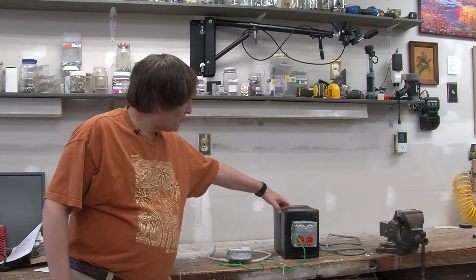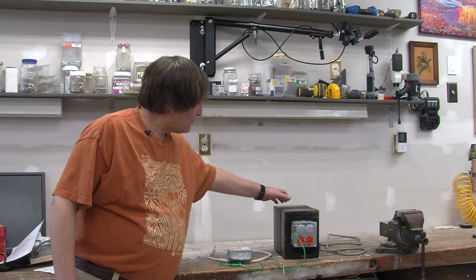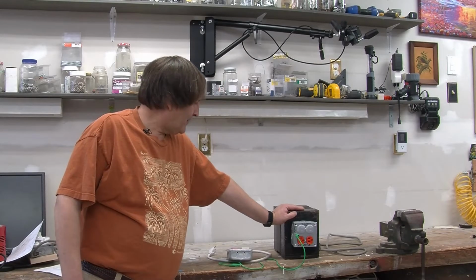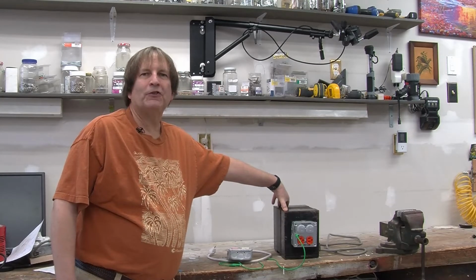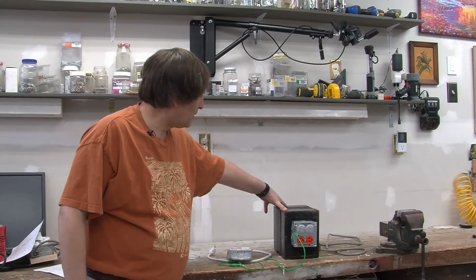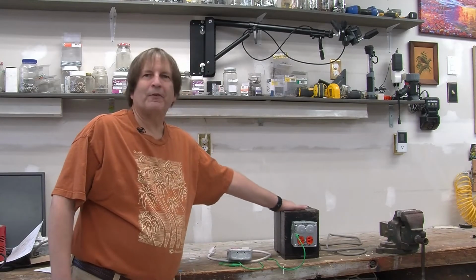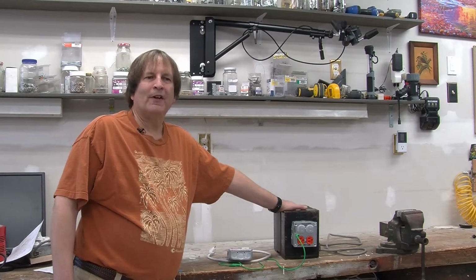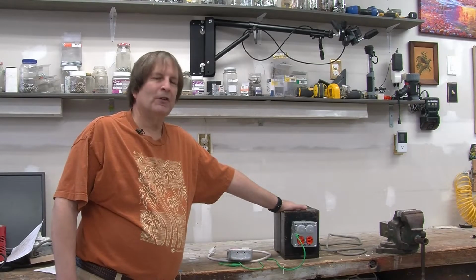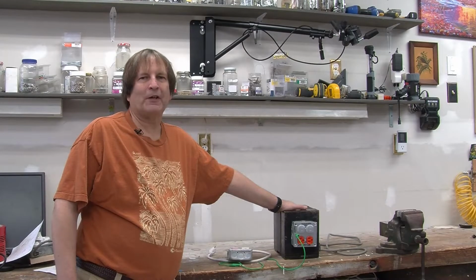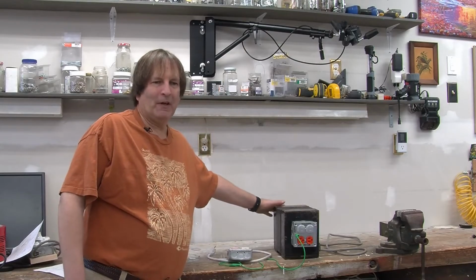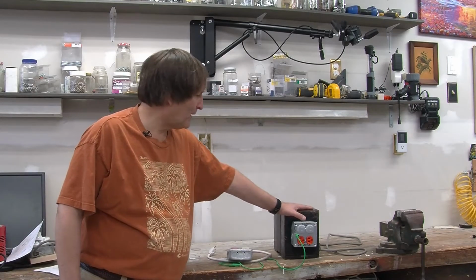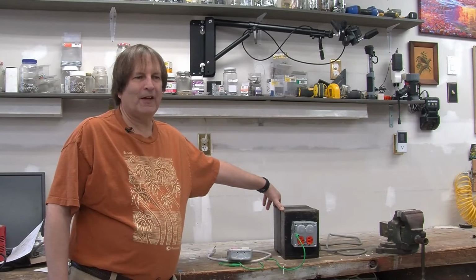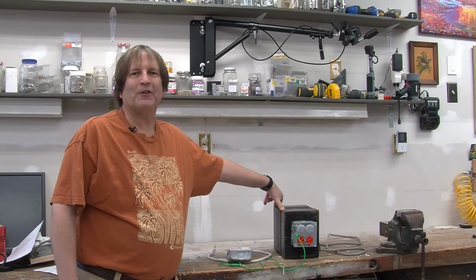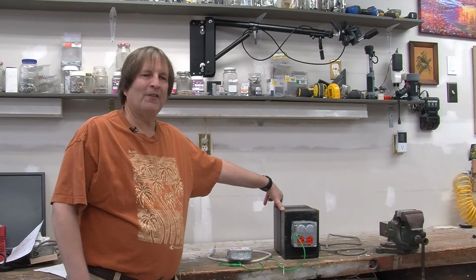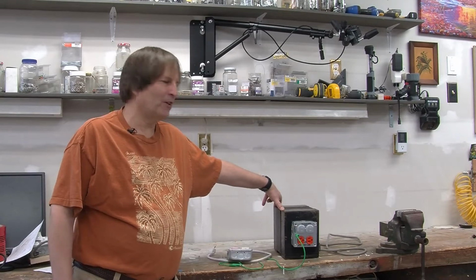There's one thing I wanted to point out if you're looking to buy an isolation transformer: there are actually two types commonly available. On places like Amazon, you'll see ones intended for audiophiles, where the whole purpose is to minimize electrical noise from the mains going to whatever device you're running. Those transformers typically have the neutrals connected together, so they're not really isolation transformers, and they're no good for the type of safety application we're looking at.